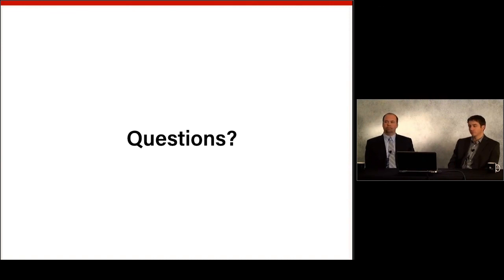All right, thanks. Another question here on LPD reduction. Was the LPD reduction from 1.47 to 0.89 achieved through fixtures alone or fixtures and controls? You indicate controls were used, but did the proposed use of controls contribute to that reduction during the design phase? That 0.89 is actually the installed watts per square foot of the fixtures at maximum. Most of the time, the store uses substantially less than that due to the daylighting and other controls in the space. We're actually 14% below what we had modeled for lighting usage in the space.